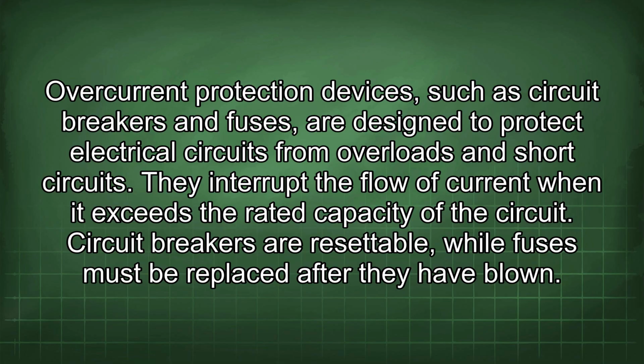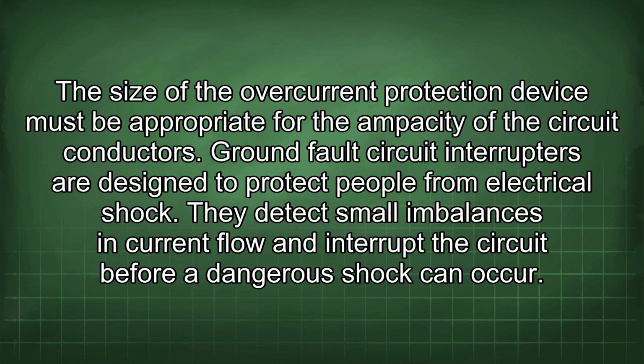Overcurrent protection devices, such as circuit breakers and fuses, are designed to protect electrical circuits from overloads and short circuits. They interrupt the flow of current when it exceeds the rated capacity of the circuit. Circuit breakers are resettable, while fuses must be replaced after they have blown. The size of the overcurrent protection device must be appropriate for the ampacity of the circuit conductors.